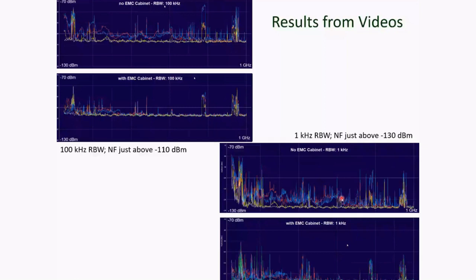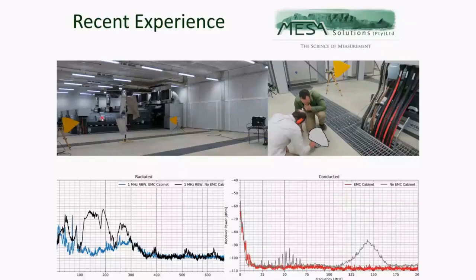Let me give you an experience which frightened me. It frightened us because we ourselves know about the weakness of not using the EMC cabinet. This is a picture of 3 diesel generators, about 1.2 MVA, sitting in the Karoo in those telescopes that I showed you. And they're in a bunker which MESA helped to design the EMC properties of. What we're doing with these diesel generators, all of the walls are reinforced concrete where the reinforcing has been tightly put together. No cables enter this building or exit this building except at one point.